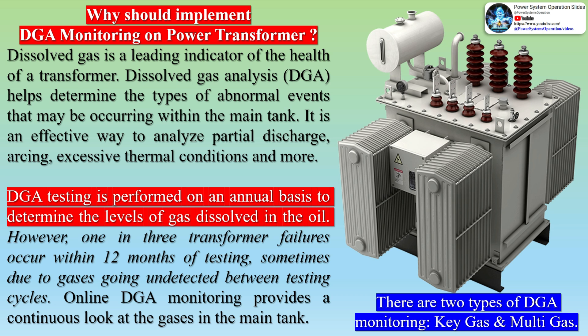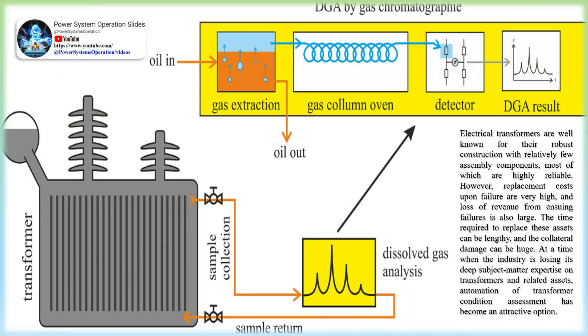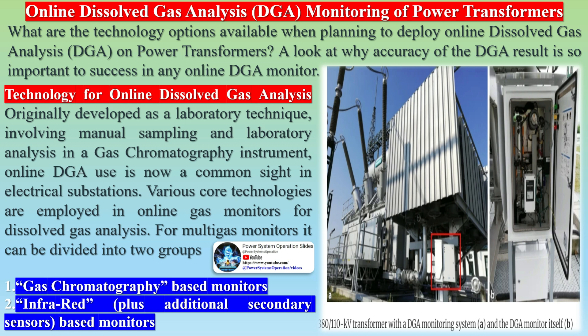What are the technology options available when planning to deploy online Dissolved Gas Analysis (DGA) on power transformers? Originally developed as a laboratory technique involving manual sampling and laboratory analysis in a gas chromatography instrument, online DGA use is now a common sight in electrical substations. Various core technologies are employed in online gas monitors for dissolved gas analysis.